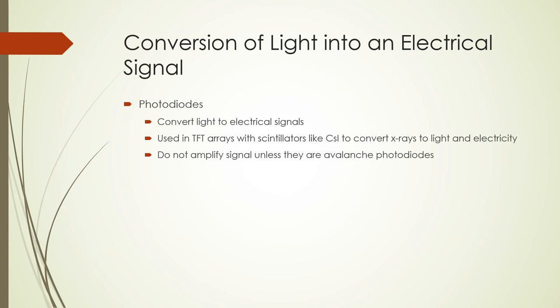Another device that converts light to electrical signals is the photodiode. In indirect digital x-ray detectors, amorphous silicon photodiodes were used in thin film transistor arrays with a cesium iodide scintillator to convert x-rays to light and electricity. Photodiodes are smaller in size than photomultipliers and can be built directly onto an x-ray detector chip. Most photodiodes do not amplify the signals, but if they are designed as avalanche photodiodes they provide some amplification, though not as much as a photomultiplier.